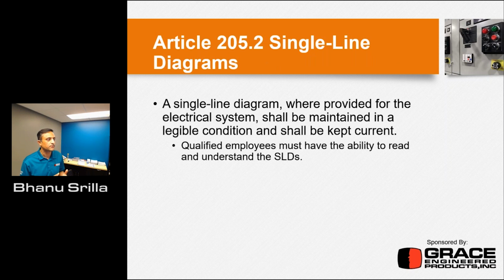So Article 205 talks about the single line diagrams. The first thing is you need to make sure the electrical system single lines are kept intact and maintained so that the person who is performing the task is capable of reading and interpreting those SLDs. Because if the SLD is not updated, if you make any kind of modifications to the trip settings or to the location of the breakers, that could change the entire thing, right? So then, though this person is qualified, he is not aware of those imminent dangers or the risk he is exposed to, or there could be a change in the trip settings that could put a different arc flash category on the same piece of equipment, which without knowing these changes, a worker working around that equipment cannot foresee, okay?